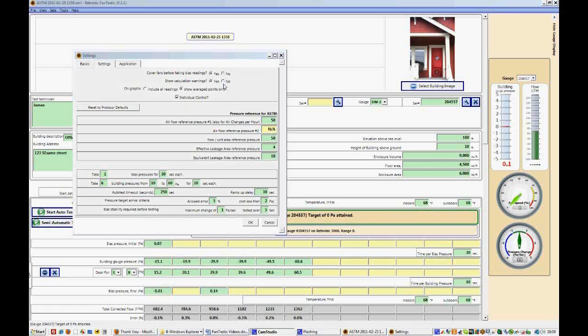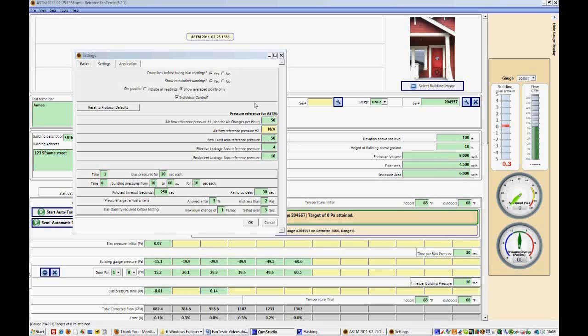When you select Show Calculation Warnings, a popup will appear if you don't have enough data to compute some of the results. So for instance, if you did not put in an enclosure volume, you would get a warning that came up that said it could not calculate air changes per hour. Now the warning is just to let you know that that value is not going to be calculated, but the test will still follow through, and it won't be invalid if you don't have that information. You just won't have the result of air changes per hour.